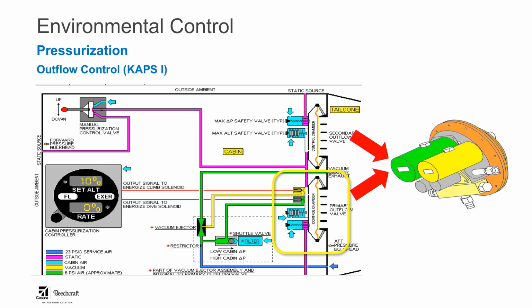That will allow the control chamber to either fill with pressure and close the valve, or be relieved of pressure and open the valve. So if you have any issue where the valve doesn't seem to change, always trying to climb or always trying to dive, you may have a short to ground somewhere either on the valve or in the wiring between it and the controller.